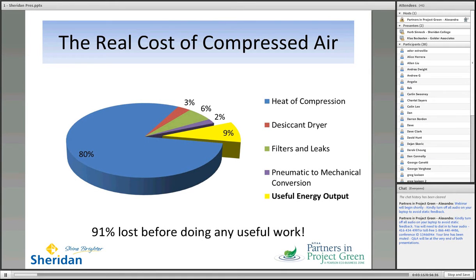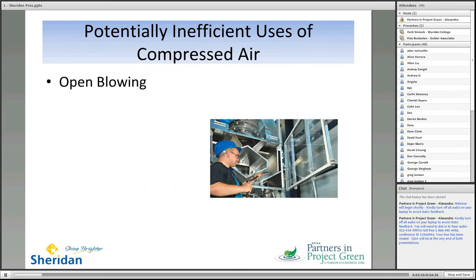The first takeaway is that compressed air is very, very expensive. You can see right away 91% of the energy you put into your compressed air system is lost before it does any practical work for you. And the bulk of that, as you see in the blue section, is just heat that arises from compressing air. As you compress air, it heats. And that heat is released primarily into the atmosphere through your receiver, through your piping, through aftercoolers, intercoolers, and all of that. And then you've got cumulative losses on top of that from systems like your dryers, your filters, leaks, and some conversion.